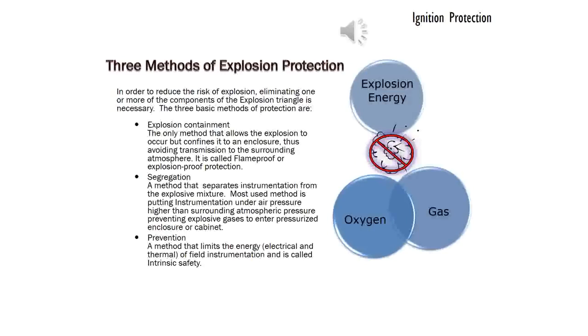necessary. The three methods of explosion protection are: explosion containment, the only method that allows the explosion to occur but confines it to an enclosure, thus avoiding transmission to the surrounding atmosphere. It is called flame-proof or explosion-proof protection.